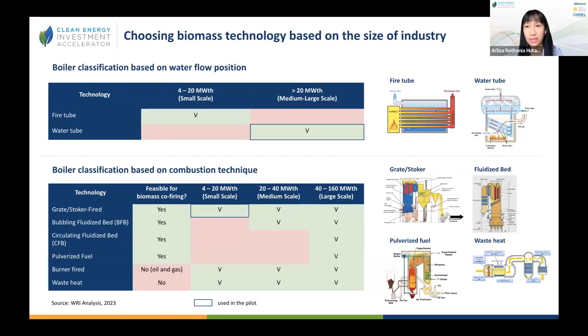Not all types of boiler classified by combustion technique are feasible for biomass co-firing, only certain types, which are the stoker fired, fluidized bed, and pulverized fuel. The other two types, the burner fired, can only use oil and gas fuel, and the waste heat, even though these two types of boiler can be applied to all scales of industrial sizes, are not suitable for biomass co-firing.